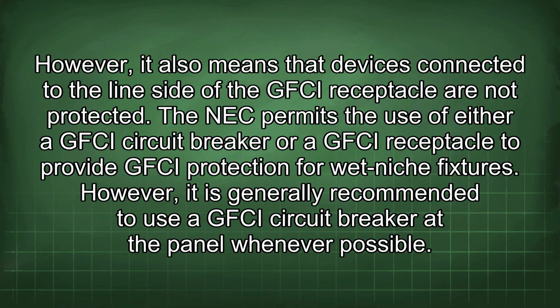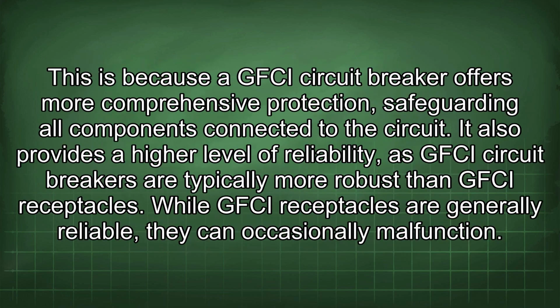The NEC permits the use of either a GFCI circuit breaker or a GFCI receptacle to provide GFCI protection for wet niche fixtures. However, it is generally recommended to use a GFCI circuit breaker at the panel whenever possible. This is because the GFCI circuit breaker offers more comprehensive protection, safeguarding all components connected to the circuit. It also provides a higher level of reliability, as GFCI circuit breakers are typically more robust than GFCI receptacles.